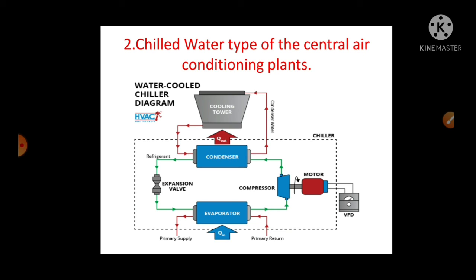Here there is an evaporator, again a vapor compression cycle. Here is the evaporator where this water comes, and it is generally a shell and tube type evaporator. Water gets cooled and this chilled water is supplied to the AHU, where by absorbing the heat from this water, the liquid refrigerant is converted into vapor. These vapors are sucked by the compressor and passed to the condenser. Again here the condenser is a shell and tube type, water cooled condenser, and this heat is supplied to this water. This water is again passed to the cooling tower where the heat is rejected to the air.